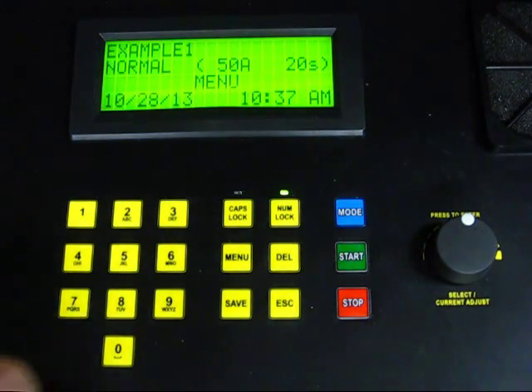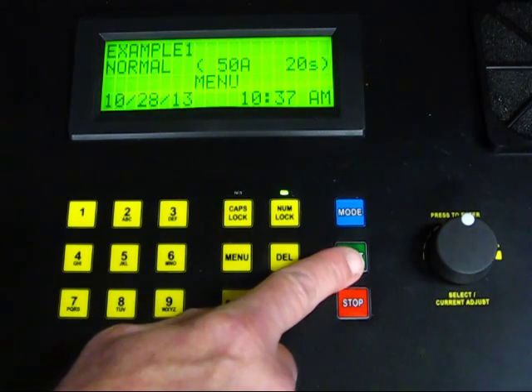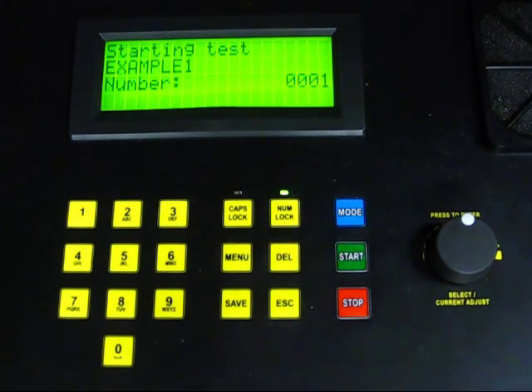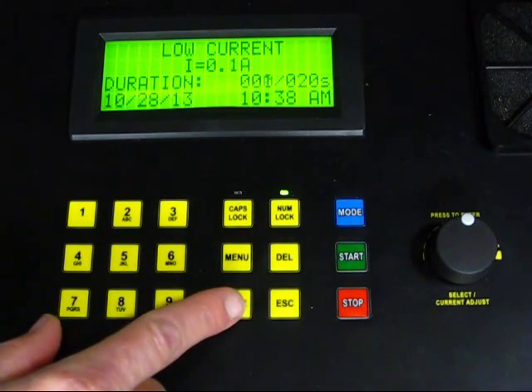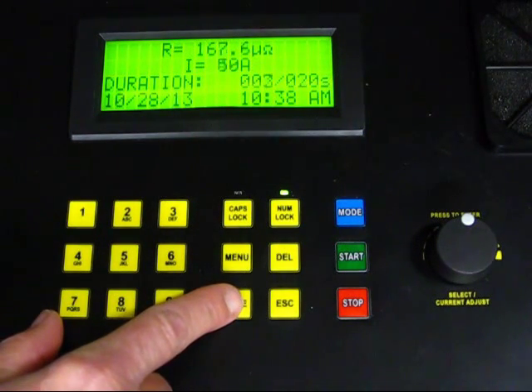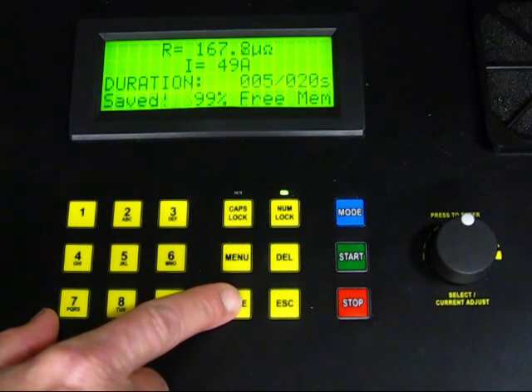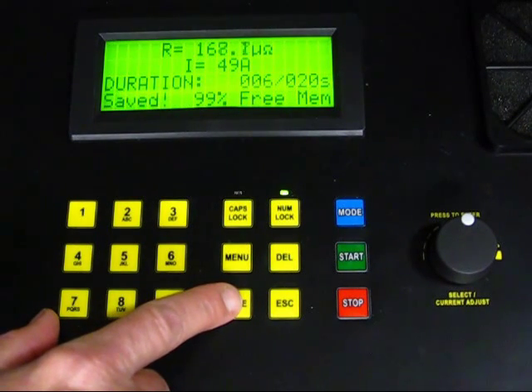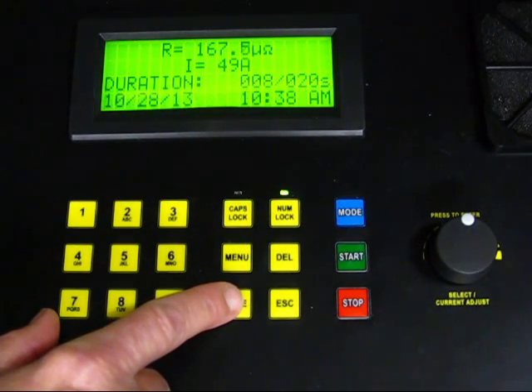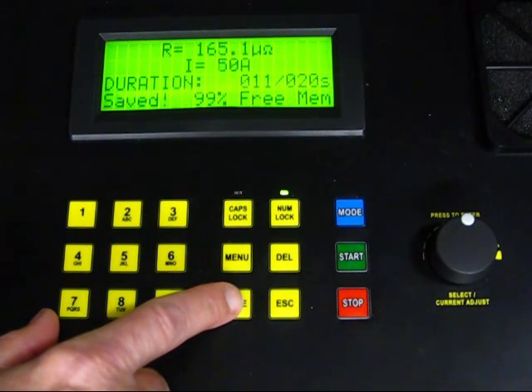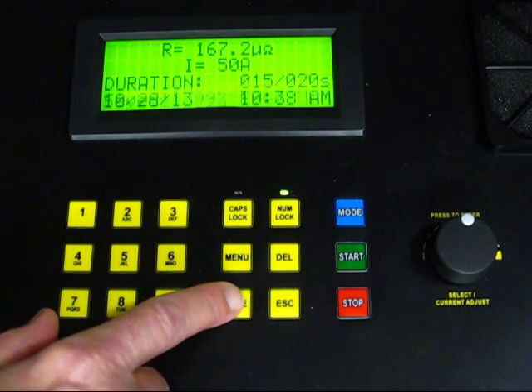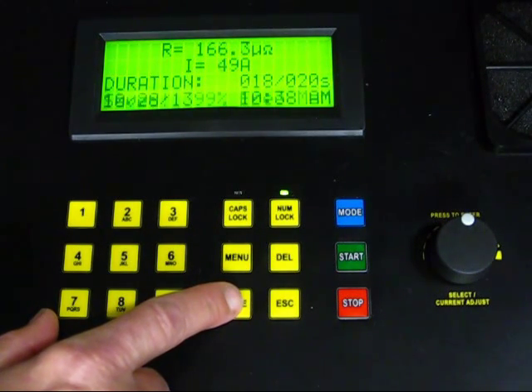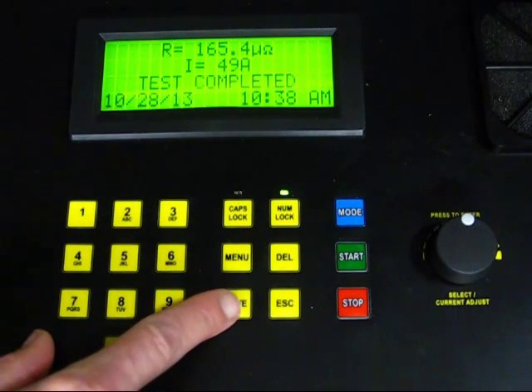To begin the test, press the green Start button. After a few moments, the LCD display indicates the test is underway. A feature of the Model 6292 is the ability to save partial test results. To do this, we will press the Save button every 5 seconds during the test. This allows us to save partial measurements at 5, 10, and 15 seconds as well as the complete measurement at 20 seconds. All these measurements will be stored in a test record within the object we have named Example 1.